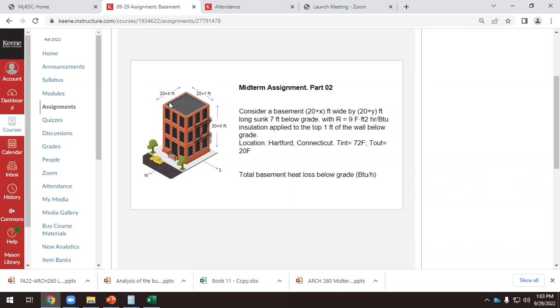So what's the final thermal load? Again, I always follow the same structure. So the last row is the thermal load, and I have to place the thermal loads on this column. So that equals, and what's the thermal load in this lesson? This is it. So it's the U value of the first foot times the perimeter times 72 minus 20. I can do this in every column. Okay, let's do this. Yesterday, I think I did something different, but what is the thermal load here? I'm going to use this. So this thermal load equals the U value of that first foot times the perimeter times the indoor minus outdoor temperature. And the indoor minus outdoor temperature is this minus this.